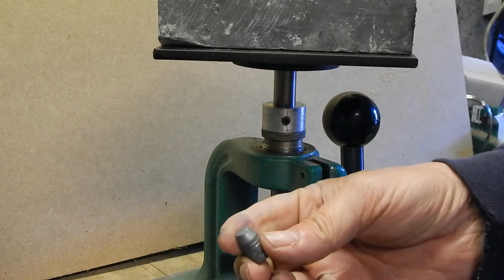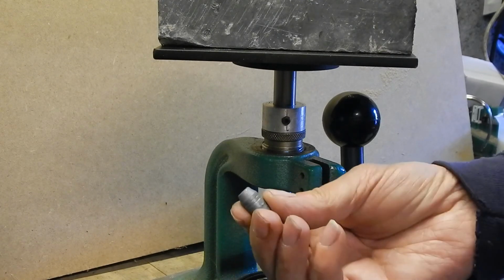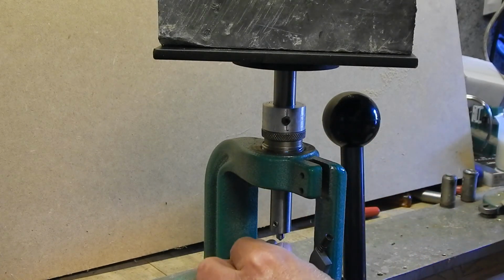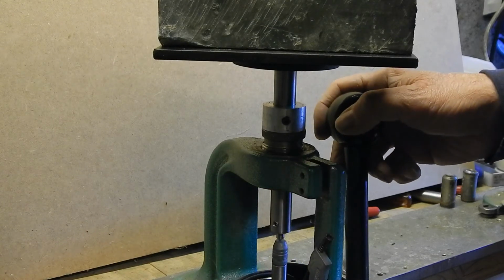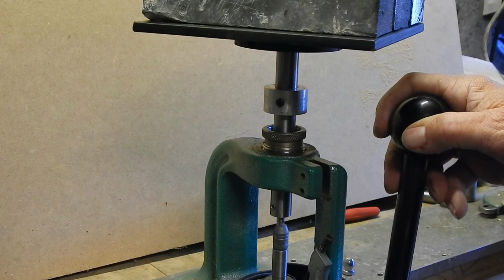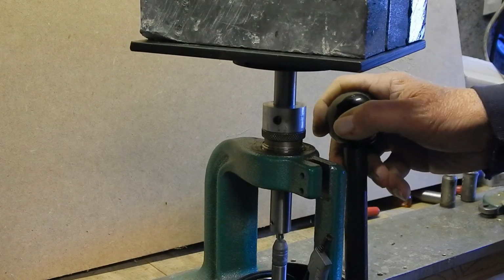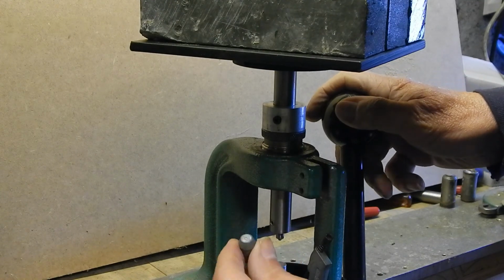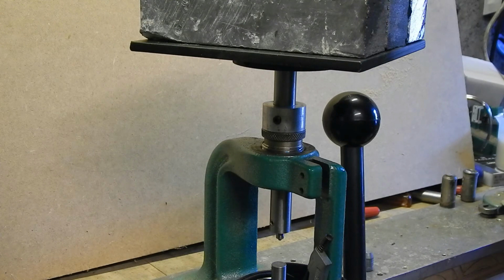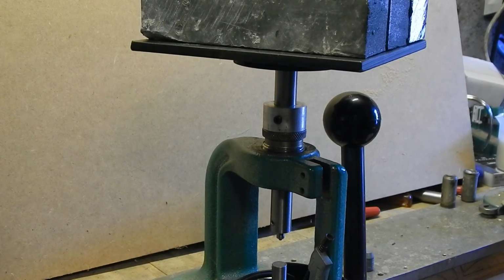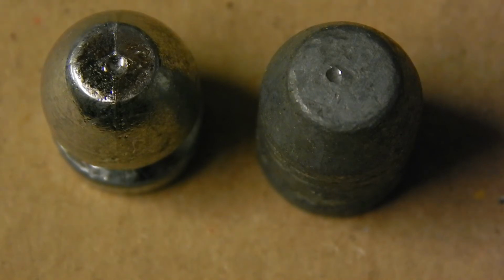This bullet is a hard cast 45 caliber bullet, which is claimed to have a Brinell hardness of 15.5. That goes on there, and again lift up the weight table, wait for the set period, say 15 seconds again, let it down. Okay, that's the test. Here are the two bullets we just tested. The pure lead one is on the left, and I think it's fairly clear that the indentation on that one is wider than the indentation on the hard cast bullet. All we need to do now is find a way of accurately measuring the diameter of those indentations.